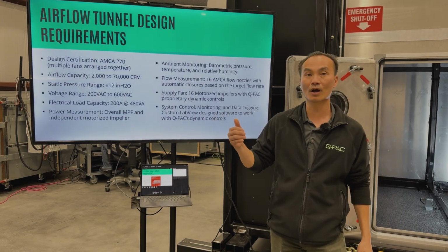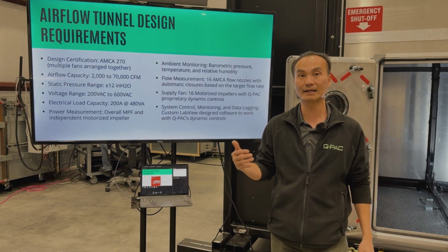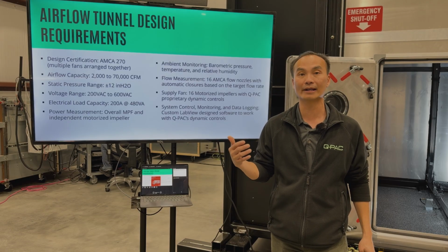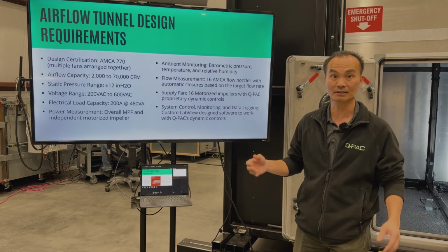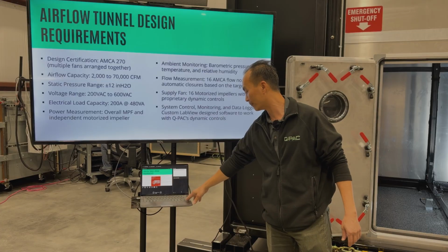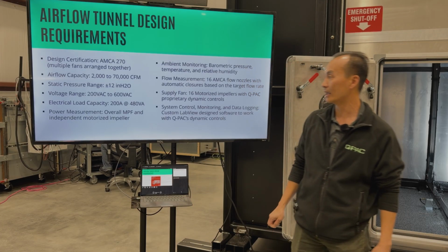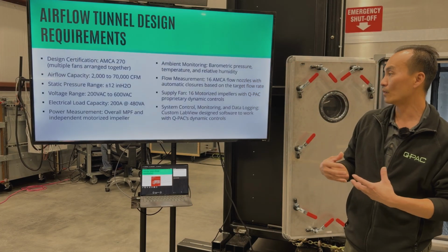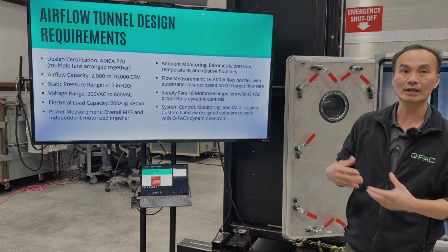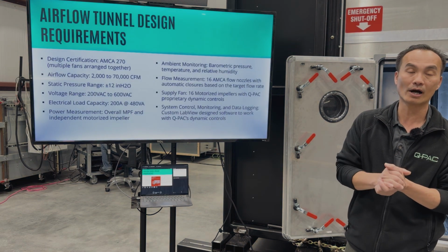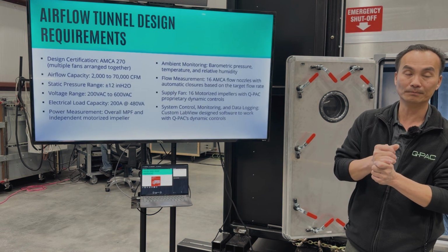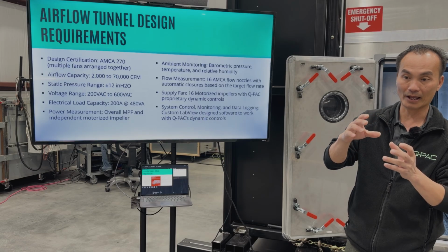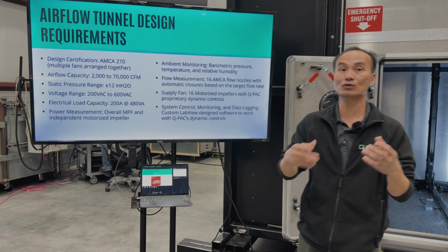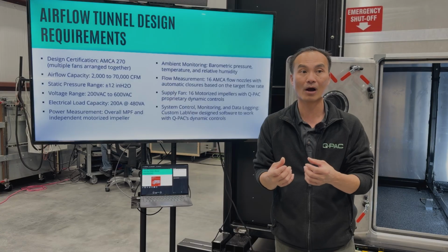We can test up to 600 volt AC and at 200 amp power. So this is a really large power that can be in here. For power measurement, we also use individual as well as multiple, like individual fan power, and as well we can use system fan power measurement.